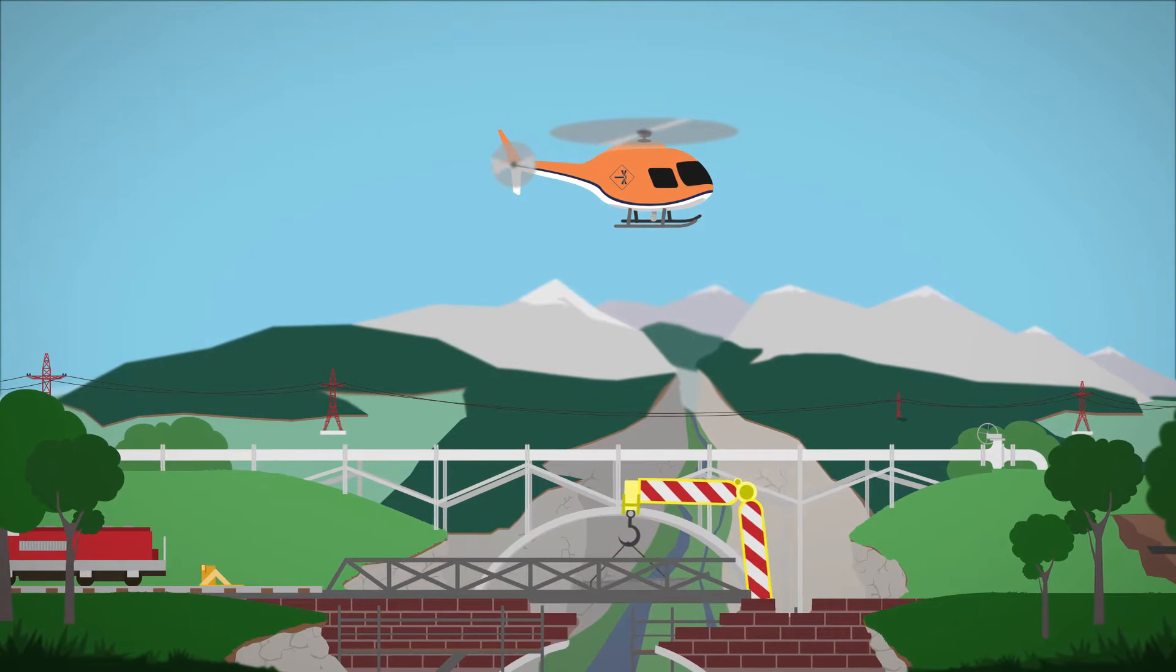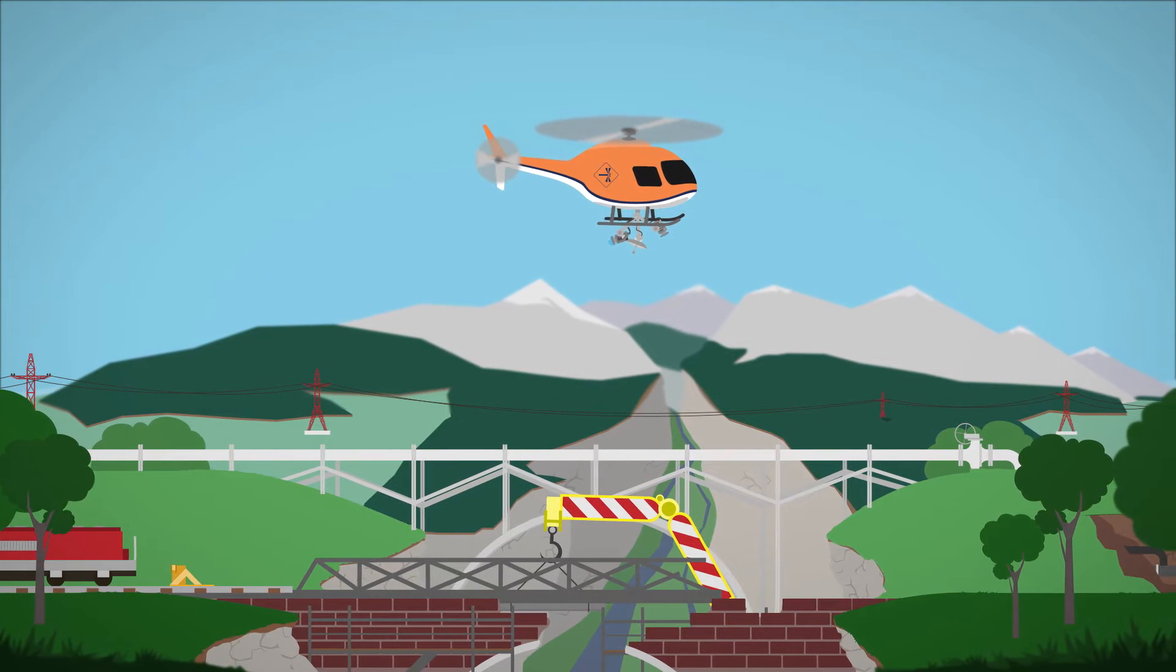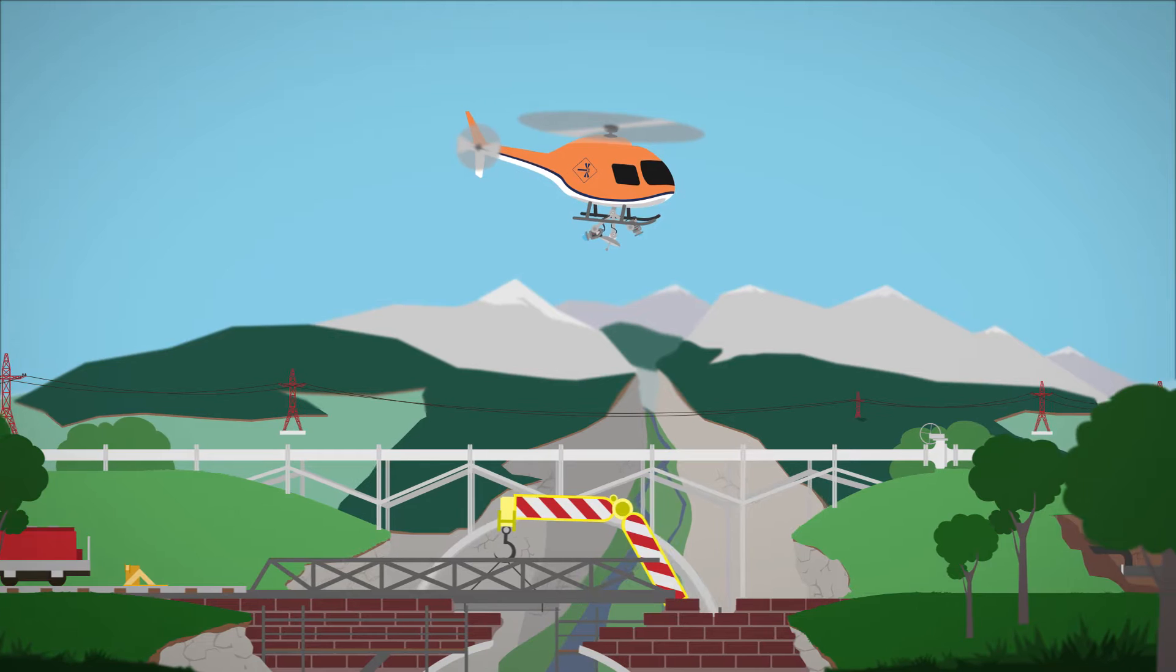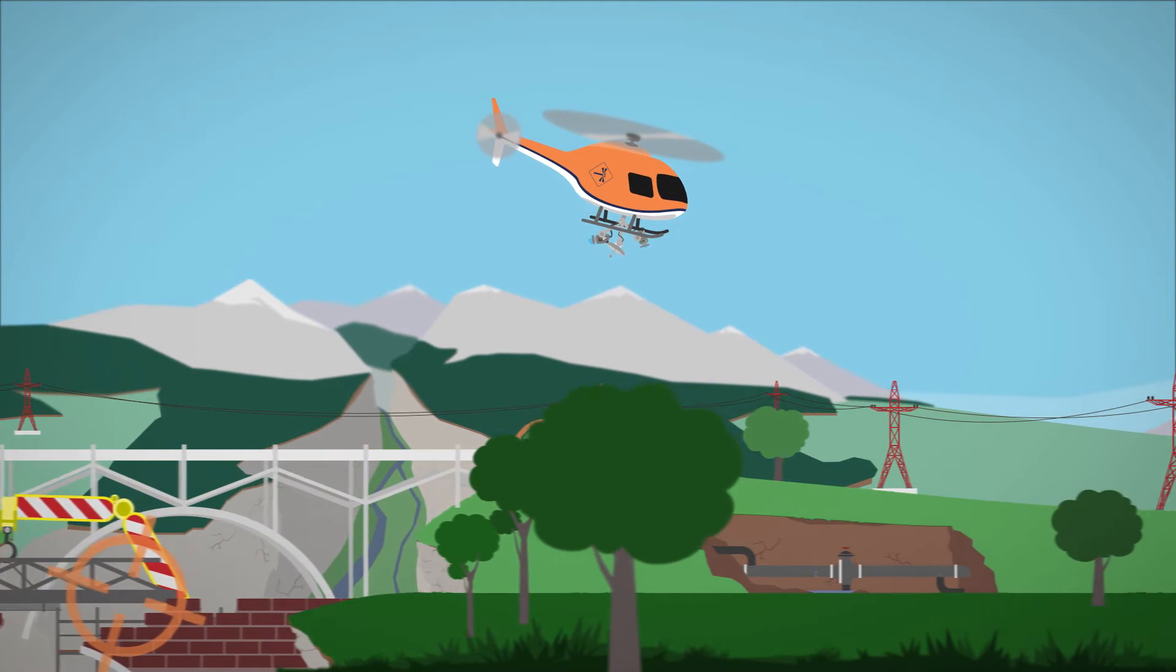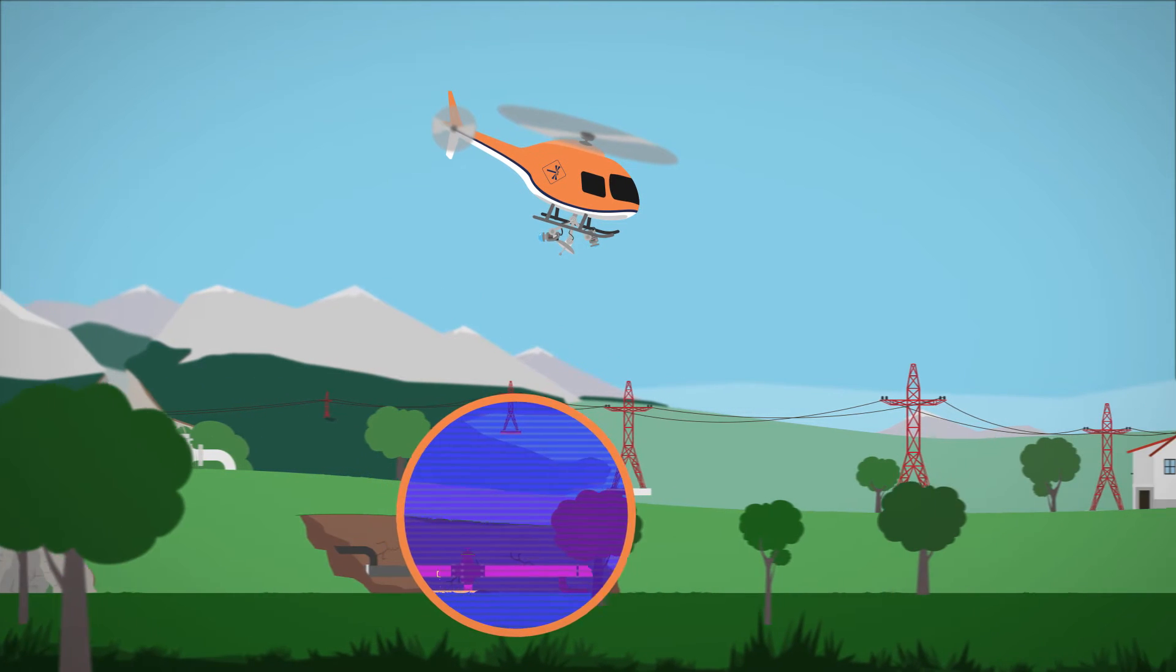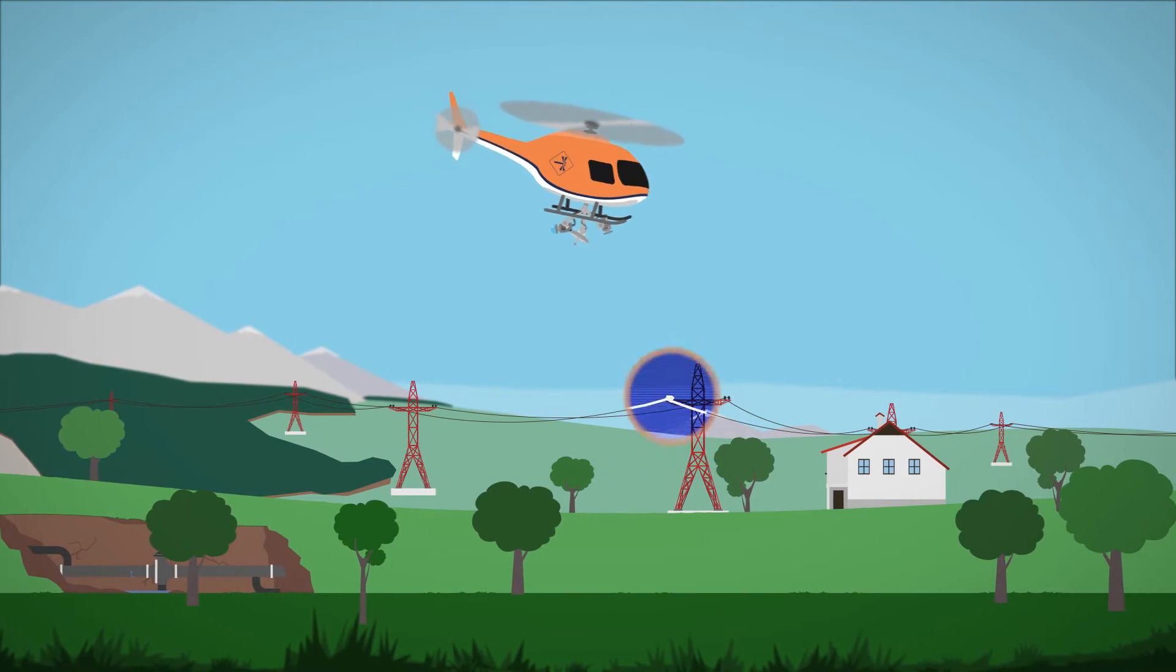Our aircrafts survey and record any given stretch of network with a set of modern technological sensors. Every discovered fault is tagged alongside recording several types of video data, like infrared for detection of overheating spots and ultraviolet used for detection of corona discharges.